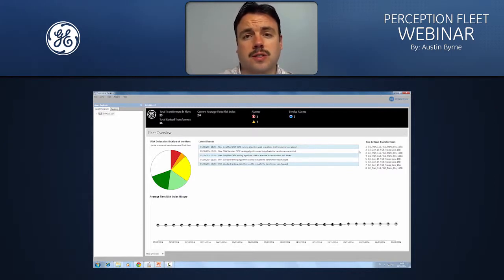The top critical transformer list on the right hand side here shows the assets which are considered to be at highest risk. So they're any assets that are in red, orange or yellow risk index, so risk index 3, 4 or 5. They're the ones that need specific attention. So they're the ones that you should be considering whenever you generate your condition-based maintenance program. They're the ones that really need critical attention.